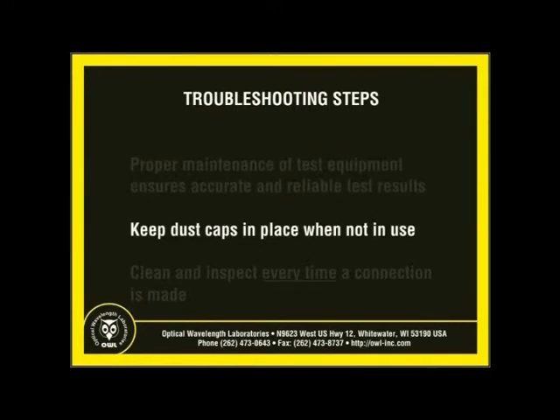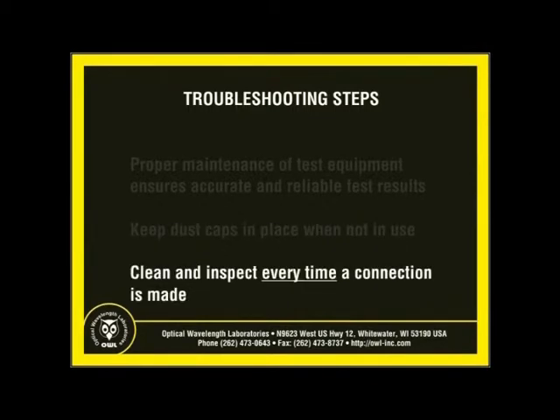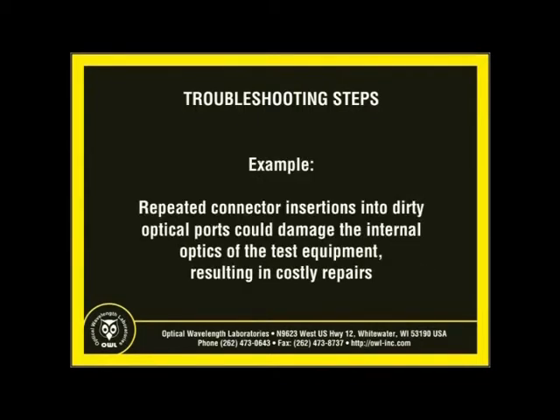When not in use, dust caps should be kept on fiber connectors and optical ports to keep debris from collecting on the surfaces of the connectors and ports. During testing, it is highly recommended to clean and inspect both connectors and optical ports every time a connection is made. Failure to properly maintain your test equipment could needlessly result in costly repairs. For example, over time, repeated connector insertions into a dirty optical port could grind the debris into the optics in an equipment port. This type of damage is permanent and cannot be repaired in the field.